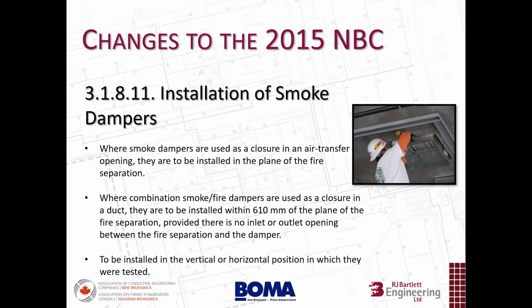And each of these dampers is to be installed only in orientations that they've been tested in. So it's always good, specifically with dampers, I find manufacturers' guidelines are often something that poke their heads up in the day-to-day questions that we receive here at RJ Bartlett Engineering. Can my firestop go around a fire damper, can I put my fire damper in this type of construction, yada, yada. It's always good to just check the manufacturer's guidelines on these devices particularly.